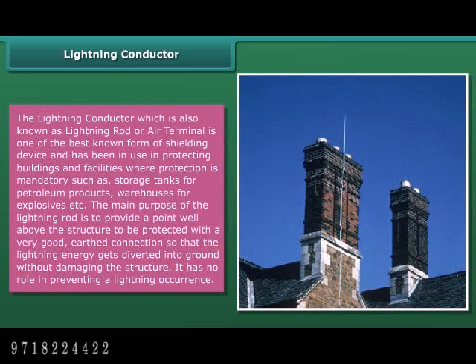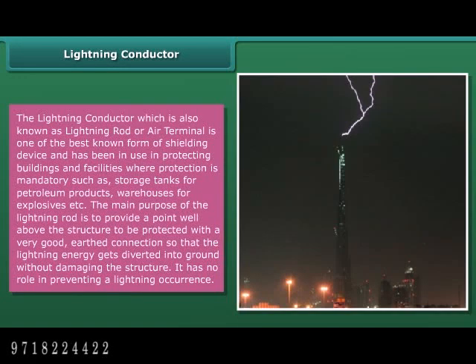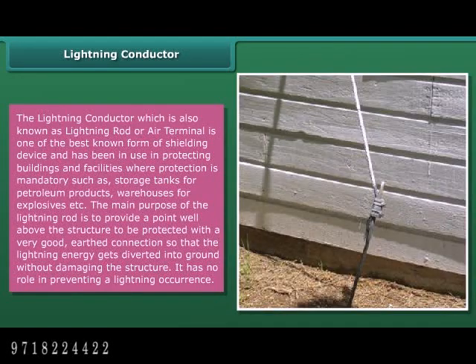The lightning conductor, also known as a lightning rod or air terminal, is one of the best known forms of shielding device. It has been used in protecting buildings and facilities where protection is mandatory, such as storage tanks for petroleum products and warehouses for explosives. The main purpose of the lightning rod is to provide a point well above the structure with a very good earth connection so that the lightning energy gets diverted into the ground without damaging the structure. It has no role in preventing a lightning occurrence.